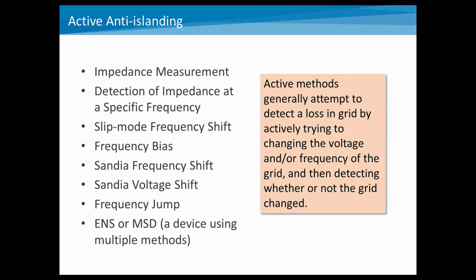So moving on to active anti-islanding techniques. So there's quite a list here of different anti-islanding techniques. These are all active. And when we say active, what we mean is that the DR is basically attempting to move the voltage or frequency around on the grid and then detect whether or not the grid has changed. So typically these work best if you have a very stiff grid. That means the DR in relationship to the size of the grid is relatively small, and the DR will not be able to move voltage or frequency around.